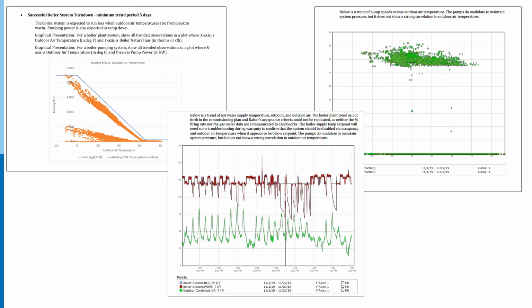And so again, we were varying between 30 degrees and 75 degrees outside. And those are the heating hot water pumps. They're just running. They don't care if it's 30 degrees or 60 degrees. There's actually 2 pumps in this system, and they're both running at 70 to 80%, like all the time. So if the design intent was to sequence those pumps, well, that's not really happening, right?